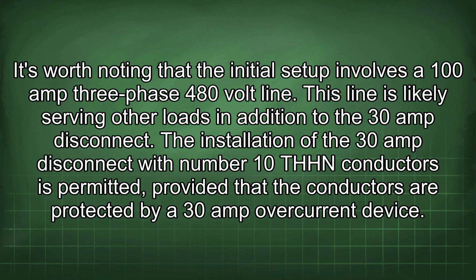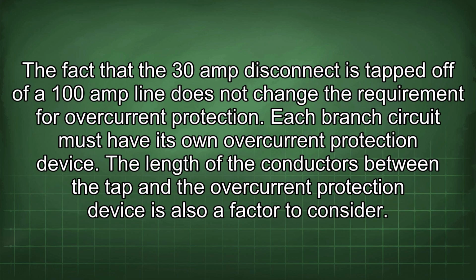It's worth noting that the initial setup involves a 100 amp 3-phase 480 volt line. This line is likely serving other loads in addition to the 30 amp disconnect. The installation of the 30 amp disconnect with number 10 THHN conductors is permitted, provided that the conductors are protected by a 30 amp overcurrent device. The fact that the 30 amp disconnect is tapped off of a 100 amp line does not change the requirement for overcurrent protection. Each branch circuit must have its own overcurrent protection device.